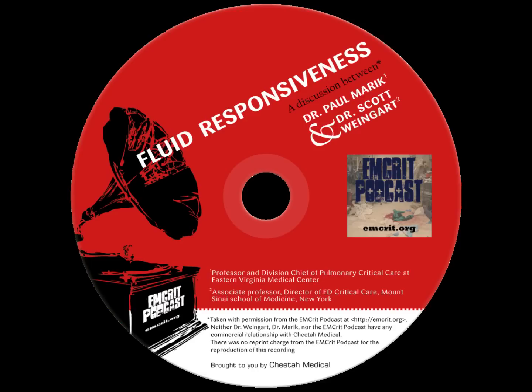With bioimpedance, you would put stickies on the chest and inject electromagnetic current. The sensors then receive the current, and by looking at the change in amplitude of the wave, you would infer that it was due to movement or change in volume of blood in the aorta, and that was stroke volume. The problem is it was affected by body shape, by obesity, by pulmonary edema, and by the distance between the electrodes. With bioreactance, you have two sets of electrodes, put on either side of the body, just below the clavicles and just at the bottom of the chest. The two outer electrodes transmit the signal, and the two inner electrodes receive the signal.